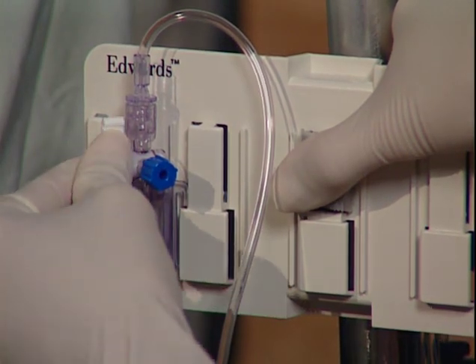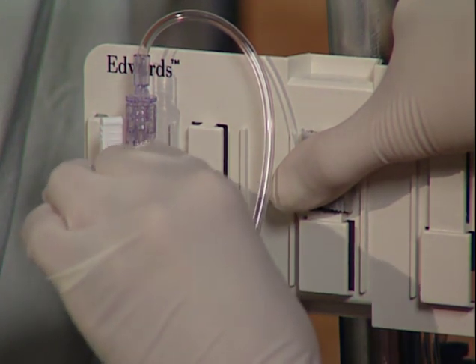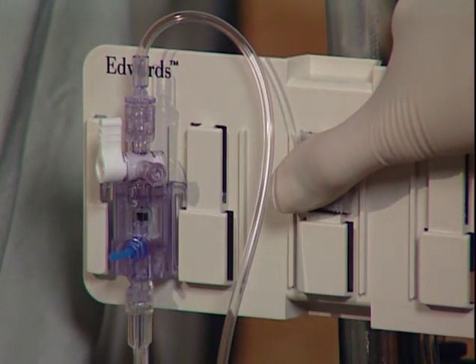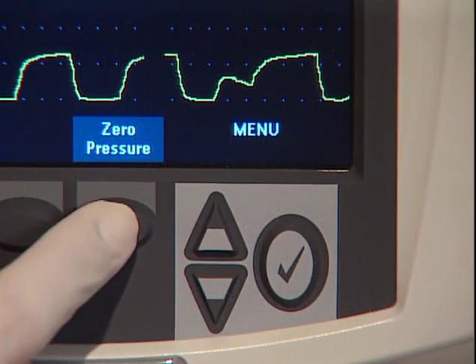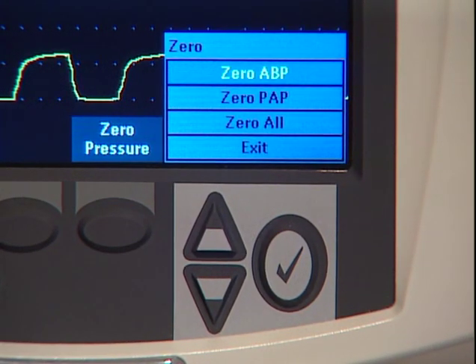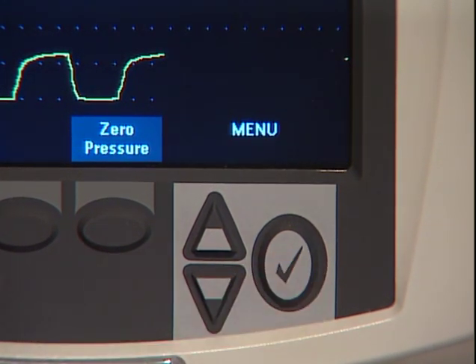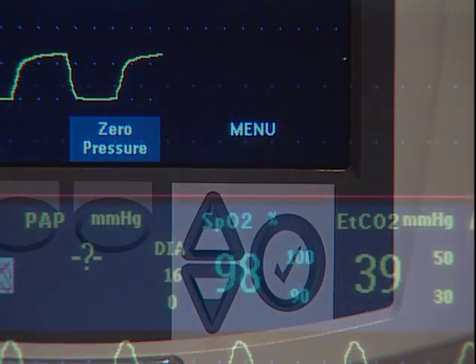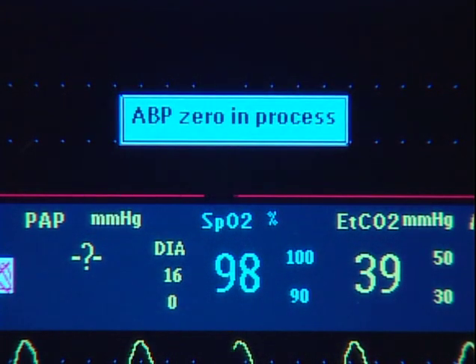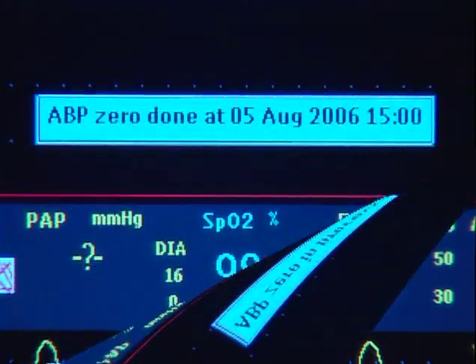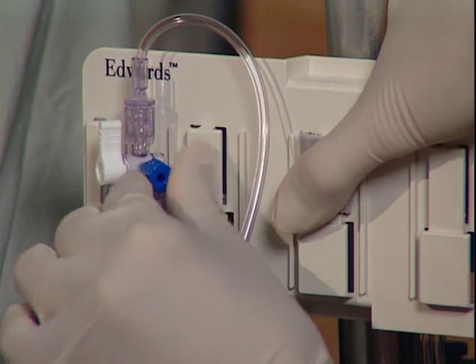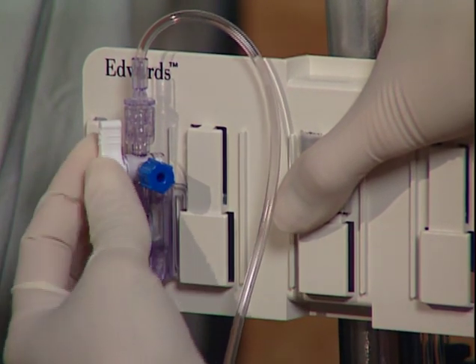First, turn off the stopcock to the patient and open the transducer to atmosphere. Press the button under zero pressure on the display. Notice you can zero one or both pressure channels. Navigate to and choose the pressure you want to zero. Then press the menu Select button to acknowledge your selection. Zeroing begins and this message appears. When you see this message, close the stopcock to atmosphere, which opens the stopcock to the patient.